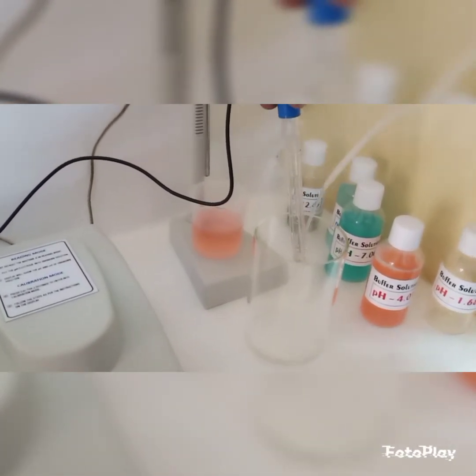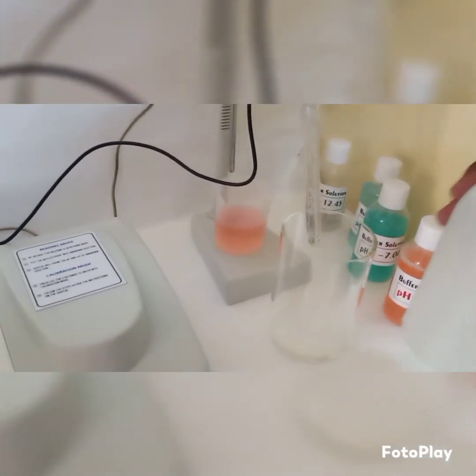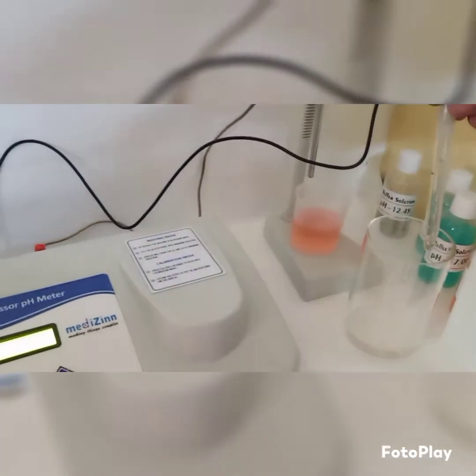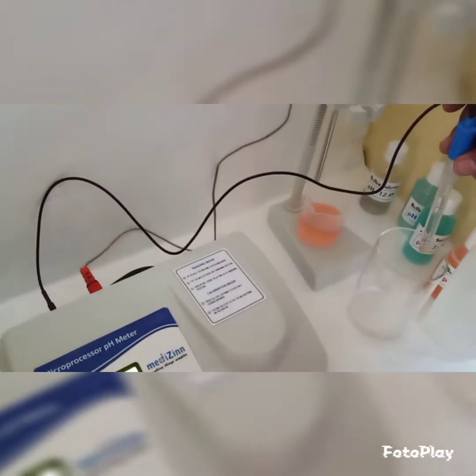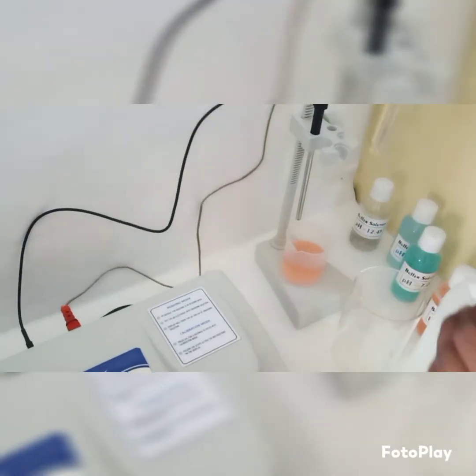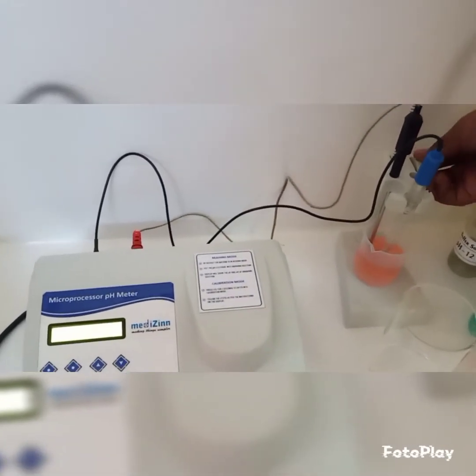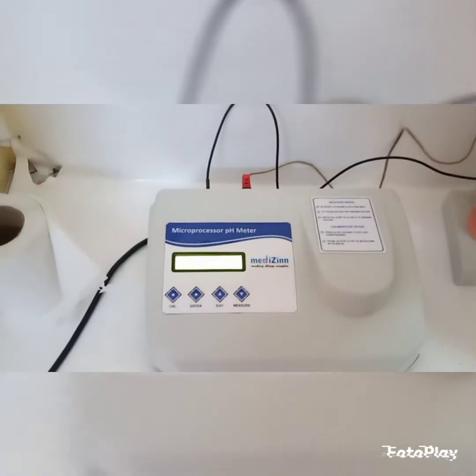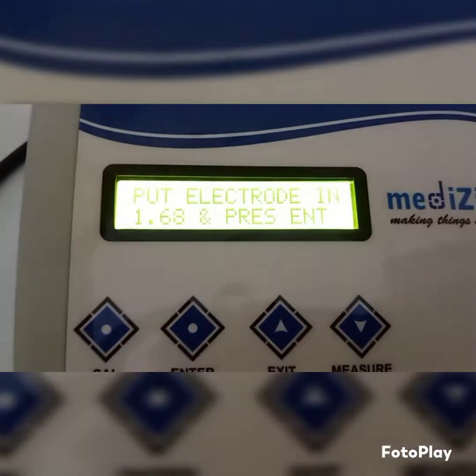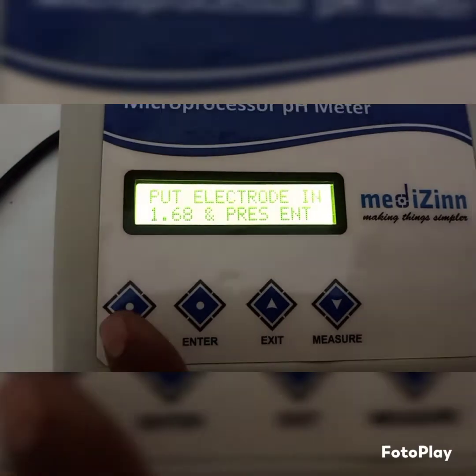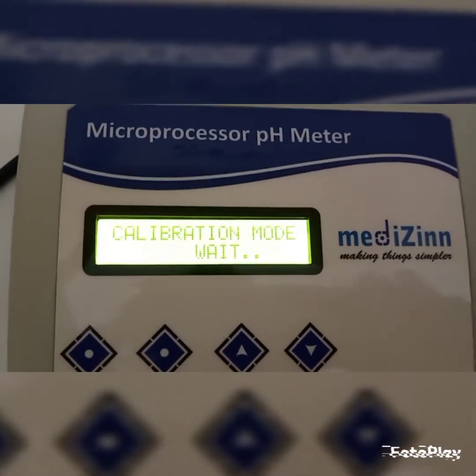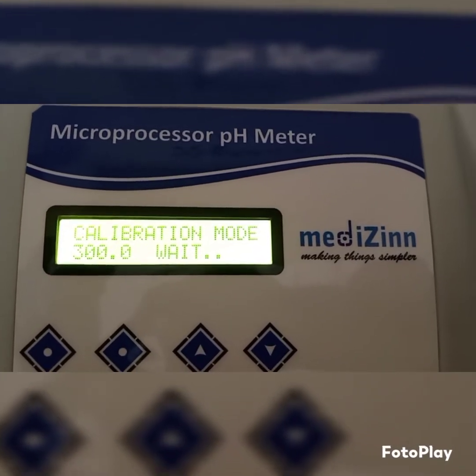Before putting into 1.68 pH, wash the electrode thoroughly with the distilled water, and clean it with tissue paper. Make sure that pH electrode and temperature probe tip touch the solution. After that, press enter. Now we have to wait for approximate 2 minutes.